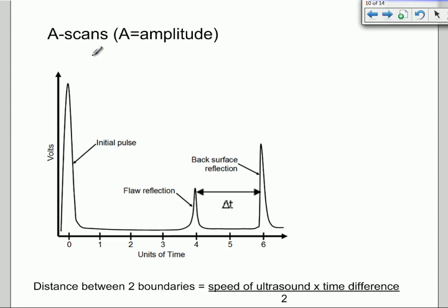The A stands for amplitude, because all we're getting is amplitude information and nothing else. So at time t equals zero, that's when the ultrasound pulse is sent out, and so we're going to get a large reading on the voltmeter as the piezoelectric transducer is vibrated. The voltmeter reading the vibrations and measuring the induced EMF will record a large pulse at that point.